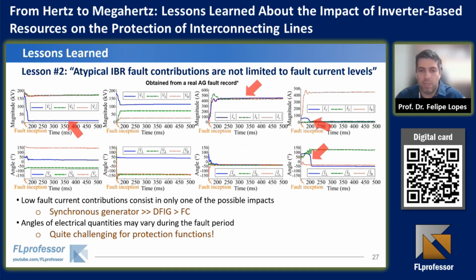So we started to understand that it depends on the fault, it depends on the system groundings, but we could see that there is a very relevant undervoltage in the faulted phase, and that these currents here present the same angle, which characterizes the zero sequence contribution. So we understood that this contribution was coming from the system, not from the IBR.